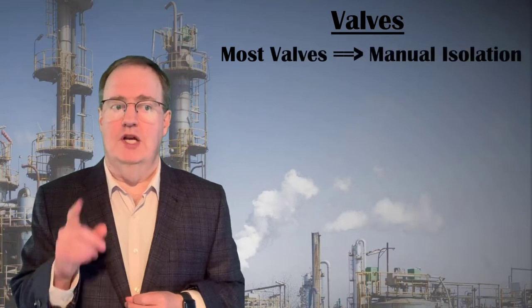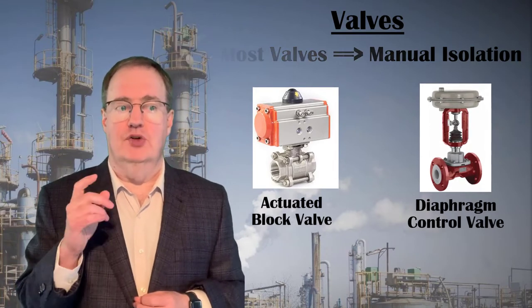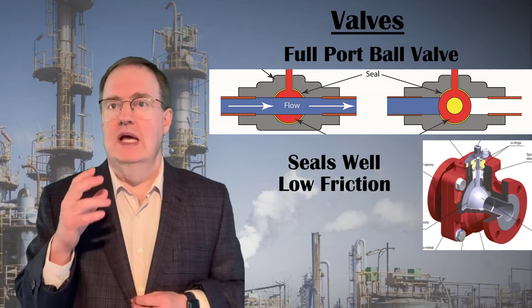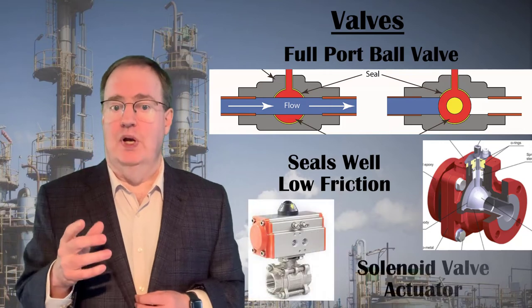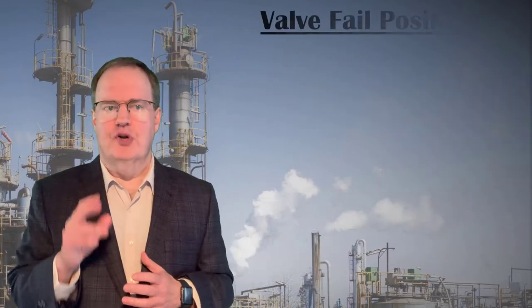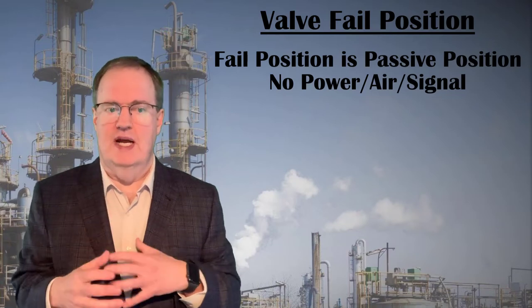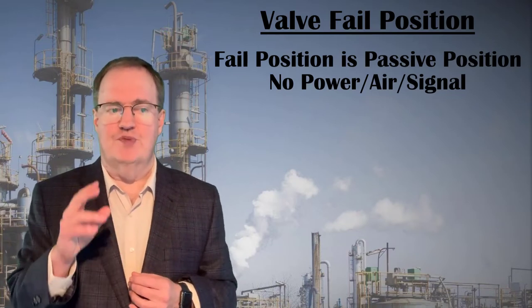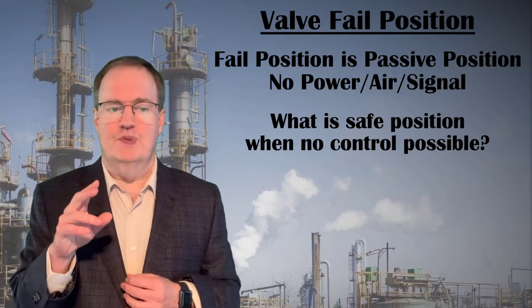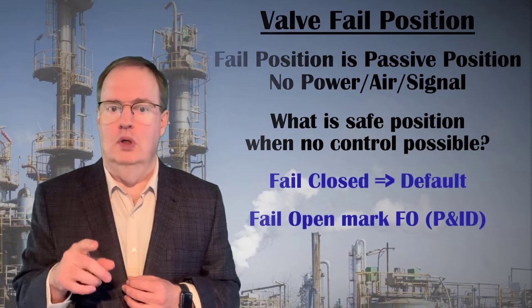There are thousands of valves in a process plant. Most are manual valves for isolation purposes, for maintenance and safety. We will focus on actuated block valves and control valves used by the control system. The most common type of actuated block valve is the full-port ball valve, which seals reliably when closed and generates no extra friction when open. Most actuators are solenoid valves that allow or stop compressed air when triggered by an electrical signal. Almost all valves have a passive or fail position — the position they revert to if they lose control signal, compressed air, or electrical power — accomplished by the action of a spring. Valves can be set up to be fail open or fail closed; engineers should choose based on which is safest. Fail closed is the default; all fail open valves should be marked F-O on P&IDs.